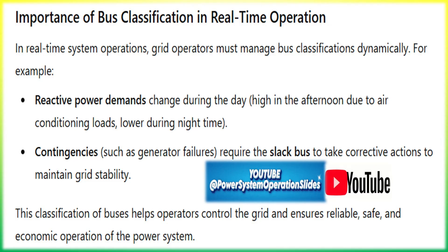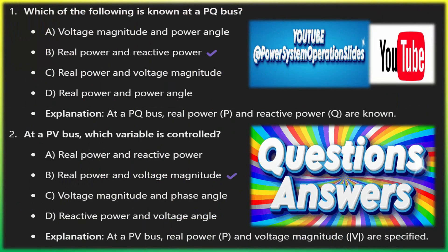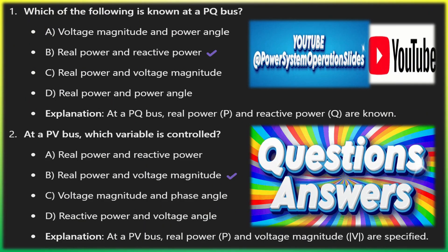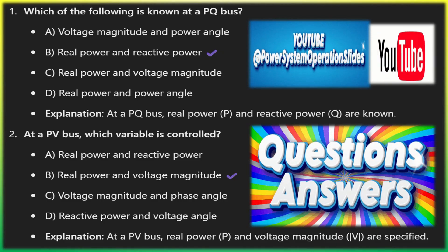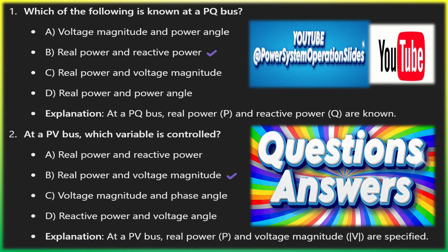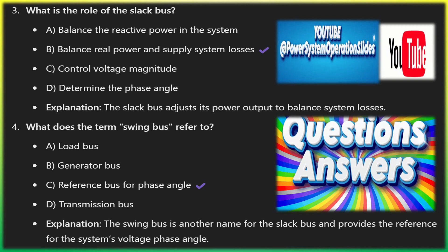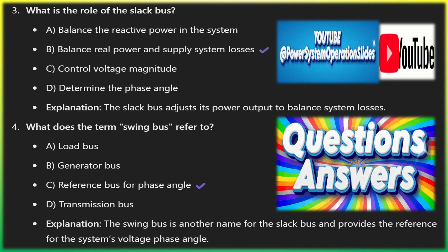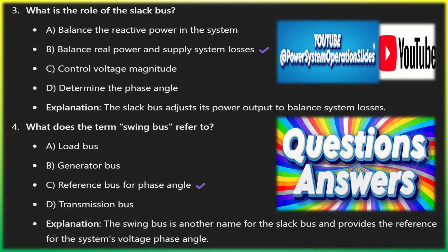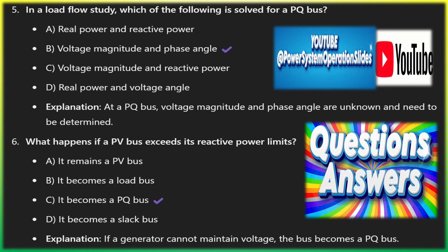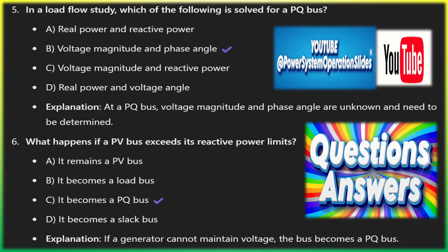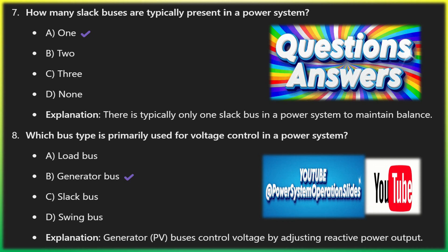Balancing real power: in any power system, total generation should equal total load plus transmission losses. However, these losses cannot be calculated directly until the load flow is solved. The slack bus provides the necessary balancing by adjusting its real power P to match system losses. Reactive power balance: the slack bus also absorbs any discrepancies in reactive power, ensuring that reactive power across the network is maintained, which is crucial for voltage stability. There is typically only one slack bus, as multiple buses adjusting for system-wide discrepancies can cause inconsistencies in solving load flow equations. The voltage angle of the slack bus is set to zero degrees, providing a reference point for phase angle calculations at all other buses.